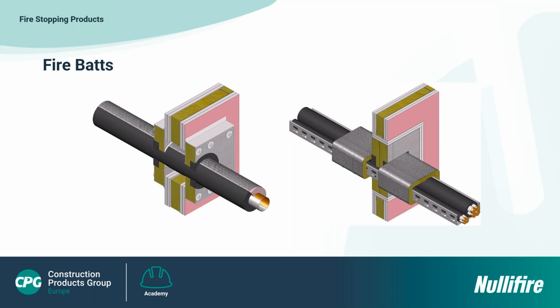They're formed of a mineral fibre bat or base, and then it has an ablative coating on both sides, which basically contains water molecules, and those particles evaporate during a fire and cool down the bat. So if combustible and non-combustible penetrations are going through that bat, the bat has to be cut and friction fitted around those, and then those have to be sealed and have either a closer device if they're combustible, or a non-closing device, or a fire stop around it if they're non-combustible.